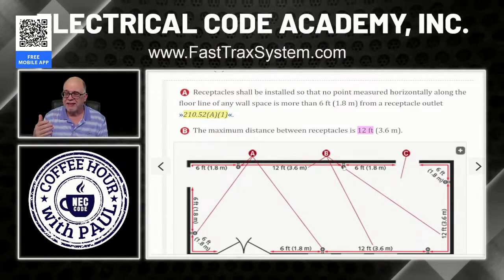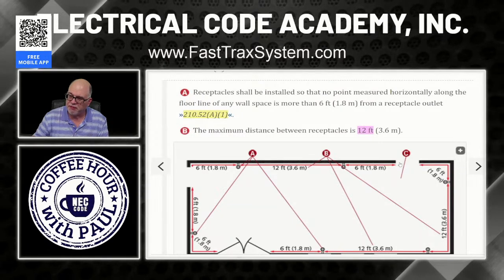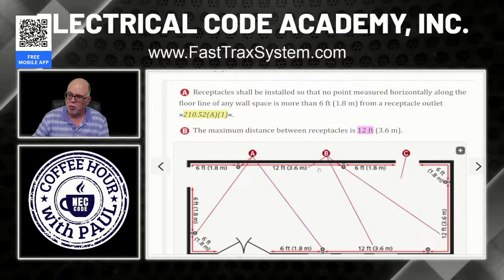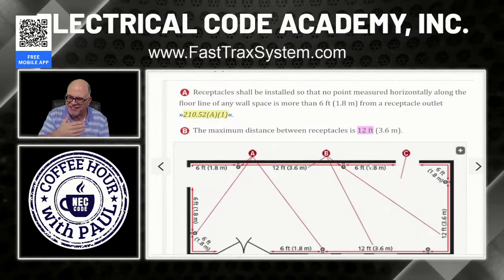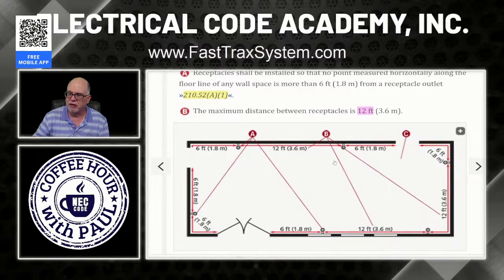Now, in the real world, that may not do. Maybe this one is 12 feet from this one, but now maybe it's 8 feet from the break in the door. What does that mean? Then you're going to have to put another receptacle here. So that usually means that instead of using this 12 feet, I'm probably going to move this receptacle a little bit to the left. Maybe it's only 8 feet from the other receptacle in order to be able to get another one in here and make it look nice on the wall. Okay, that's an aesthetic thing. And so you might have to add more receptacles to be compliant. But this drawing just shows you the minimum necessary to meet compliance.